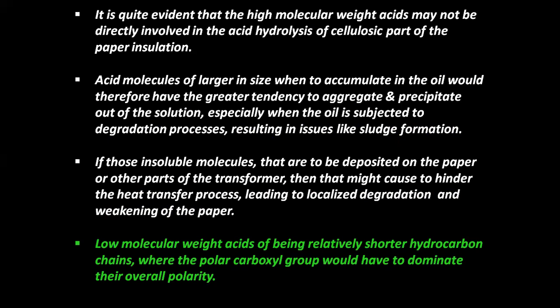If those insoluble molecules are deposited on the paper or other parts of the transformer, that might hinder the heat transfer process, leading to localized degradation and weakening of the paper.